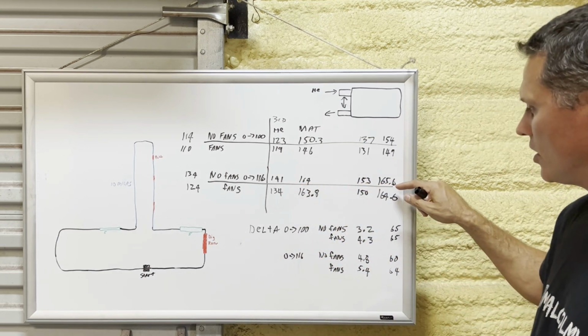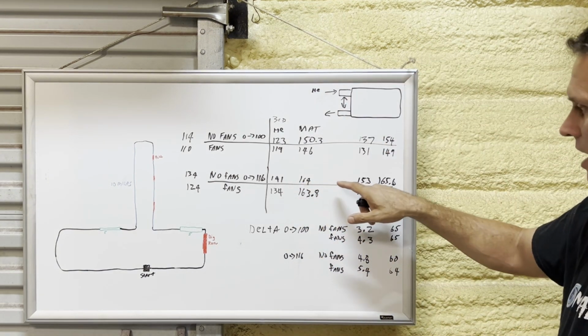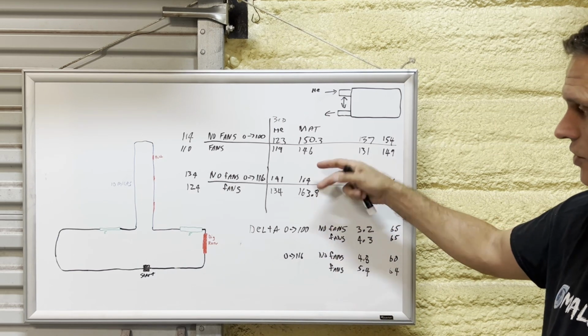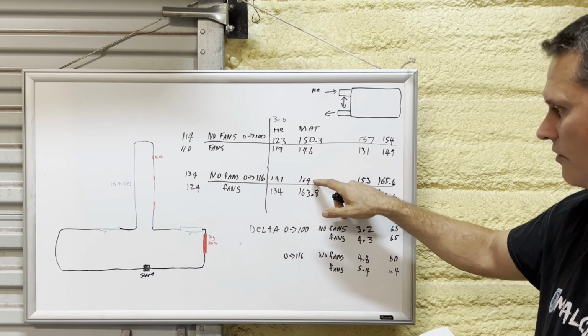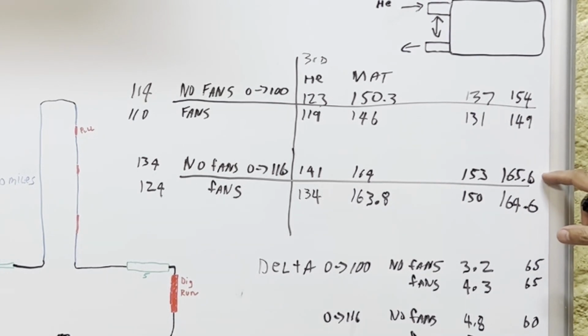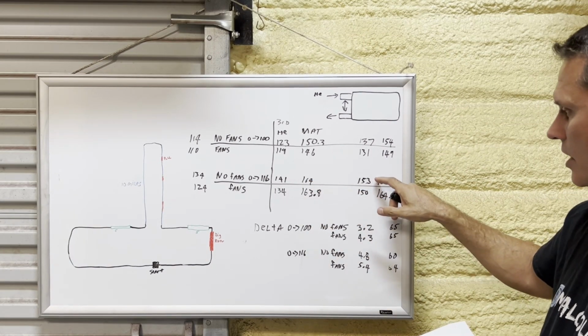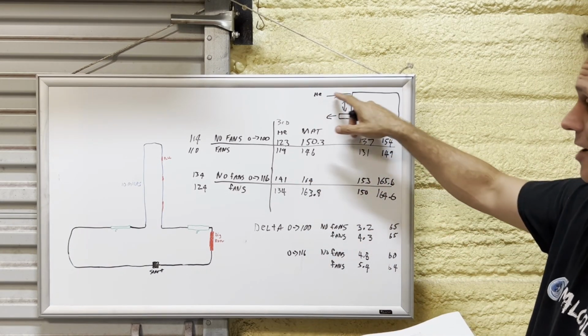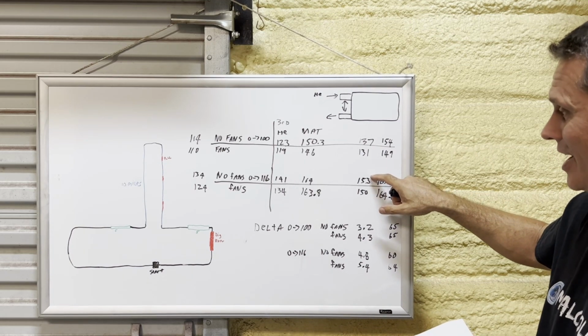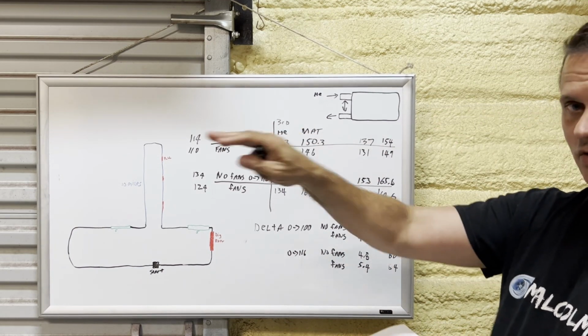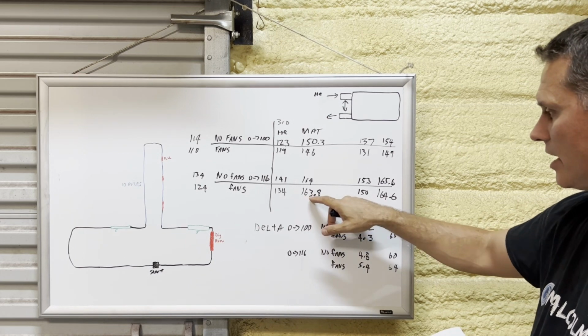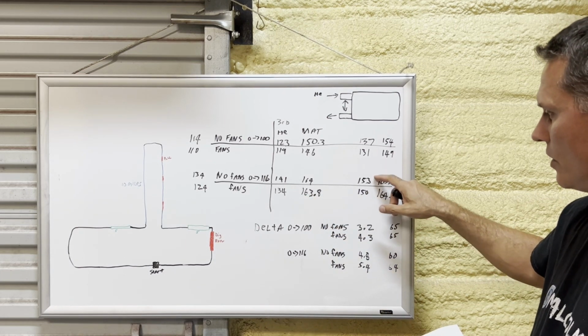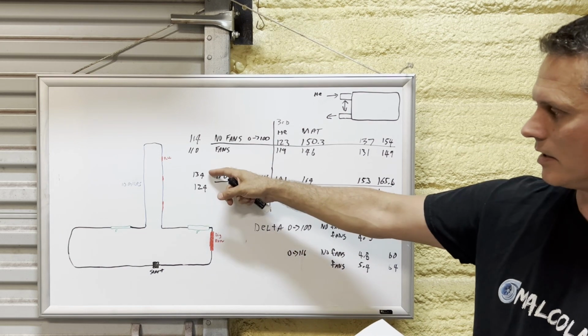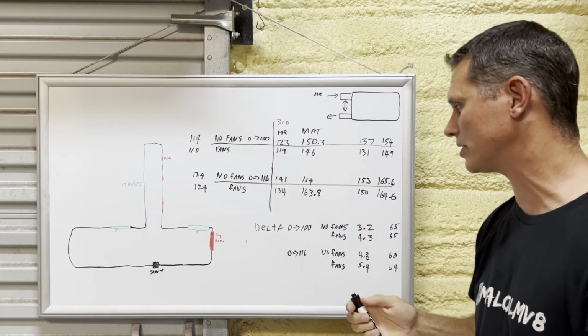And again, I charted the peaks for you so you could see after I let out, it kind of peaked, which also is why I think that it's saturated. You can see from 164, it went to 165.6, and here we went to 164.6. So they were kind of maxed out. The fluid temps, kind of interesting, 153 degrees coming into the heat exchanger here, not at the top of the run, but after I let out, the peak fluid temps. And then 150 on this one. So they came very close despite their 10-degree improvement on the start there.